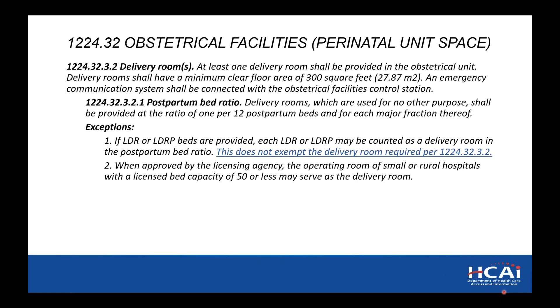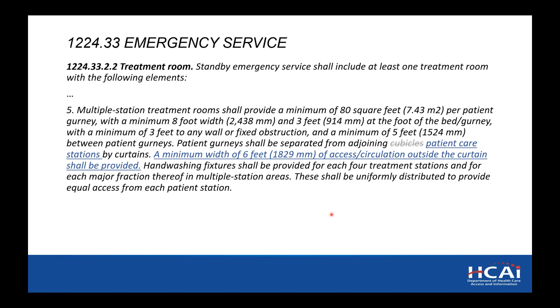Under emergency services, here again is where we're having the clearance between the cubicle curtains. Again, this is treated the same as a PACU. A minimum width of 6 feet of access circulation outside the curtain shall be provided. As I said, we're going to address these independently because they're a little different depending on where it is. And then again, this is only for the multi-station rooms, obviously. It wouldn't matter if it was in a care suite or an emergency room, so to speak, an actual room.